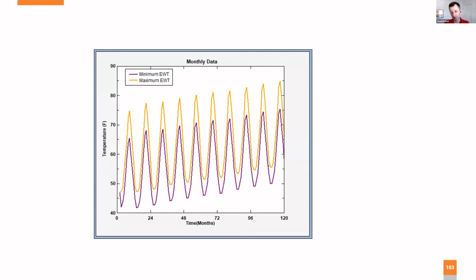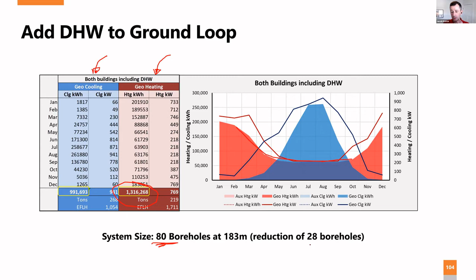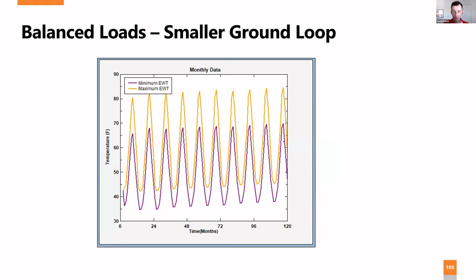But because of the energy we add to the compressor, that 1 unit of heat that we add to the compressor means that heat doesn't have to come from the ground, whereas in cooling, the heat that we add to the compressor has to also be rejected by the ground. So it's heat of compression or rejection. That means that this is actually a very balanced load. And what we were able to do is reduce the number of boreholes to 80 boreholes at 600 feet. So a reduction of 28 boreholes and a huge cost. And now we get a more balanced system that runs much more efficiently.